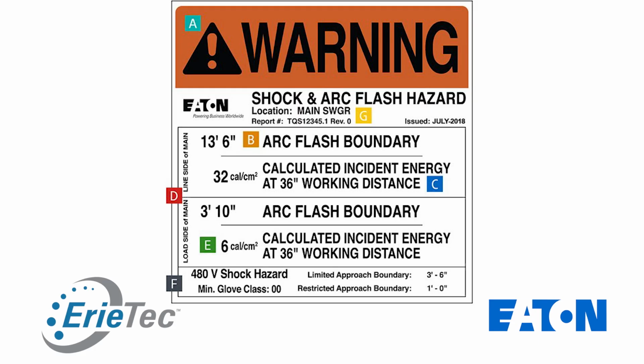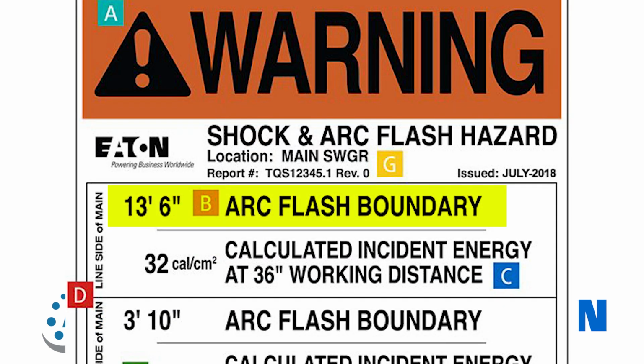Two, being your arc flash boundary. Arc flash boundary is based on the incident energy level. And that's the area that you actually have to barricade off and make sure that nobody comes into that area while you're working on the equipment live.